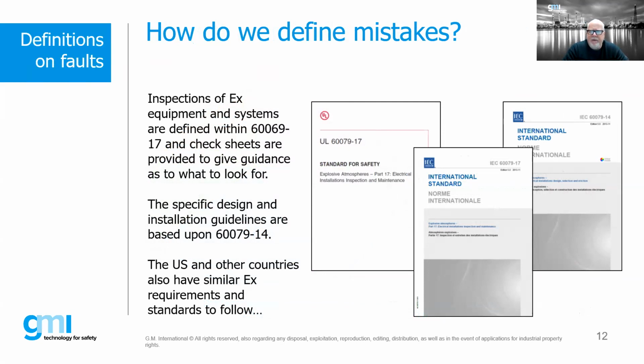The main standard to really focus your attention on is the 60079-17. I know a lot of people here are probably manufacturers or maybe users. If you're a manufacturer, you're going to follow some general standards, maybe like -0, -1, and -11. The -17 one gets overlooked by manufacturers because it deals with the inspection and maintenance of EX equipment once it gets installed.